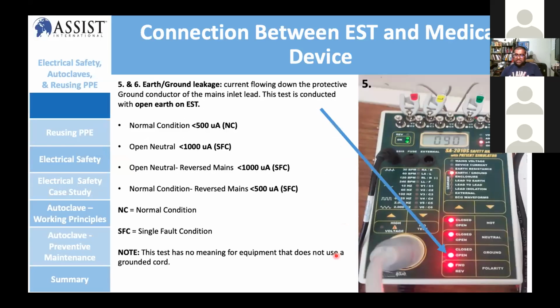So this is the connection between the EST and the medical device for earth and ground leakage. When you do earth and ground leakage, your EST intentionally opens up the ground line. It creates a single fault condition. So when you say normal condition, that means the earth is already open, and you're going to get a reading somewhere around 90 microampere. You can see the reading should be below 500, and with open neutral it should be below 1000 microamp. SFC is single fault condition, and NC is normal condition. Normal condition means your wiring and everything is in good, proper condition.